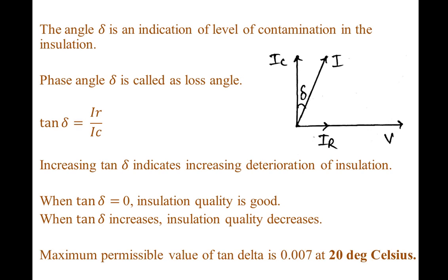The maximum permissible value of tan delta is 0.007 at 20 degrees Celsius.